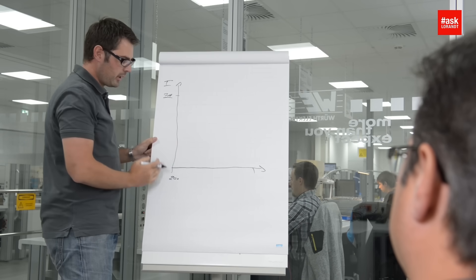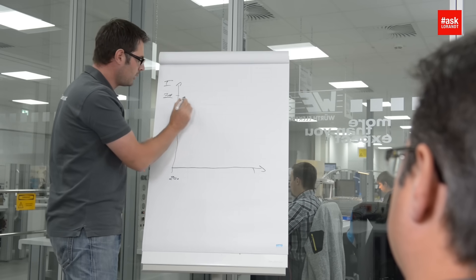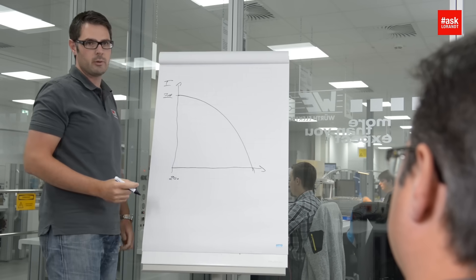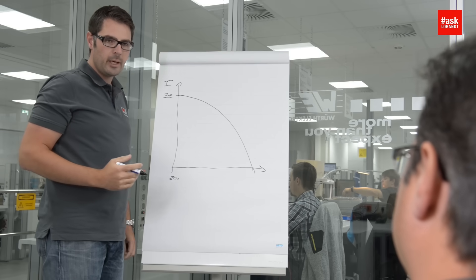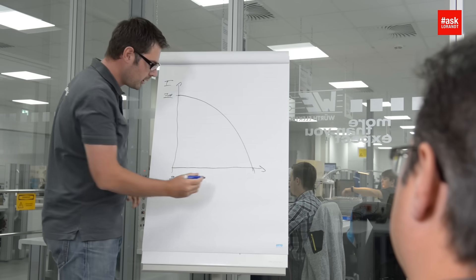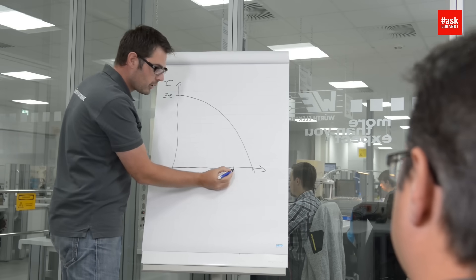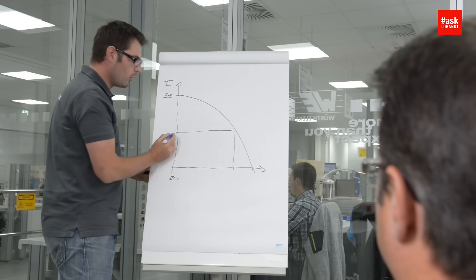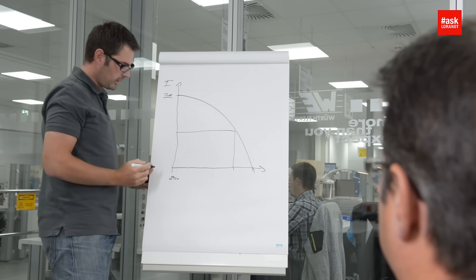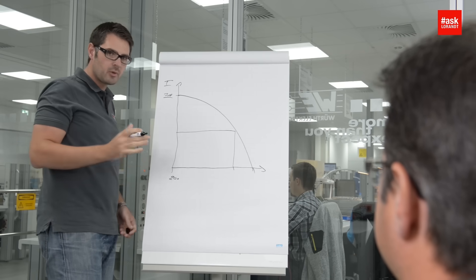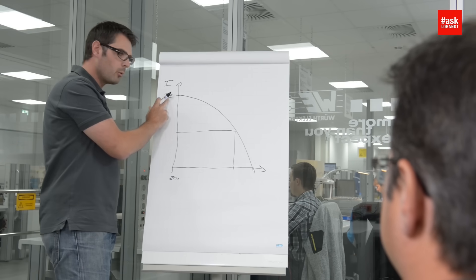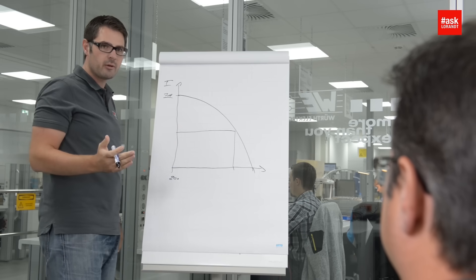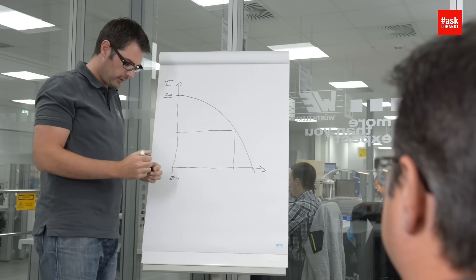And what happens? The higher the ambient temperature, the lower the current. So in your case, at 80 degrees ambient temperature, we are somewhere here on the curve. We can use that curve to analyze what your maximum current is — in that case, something like 1.5 amps. That is much, much lower compared to the rated maximum current. And that is exactly what we have to respect when we think about the derating.